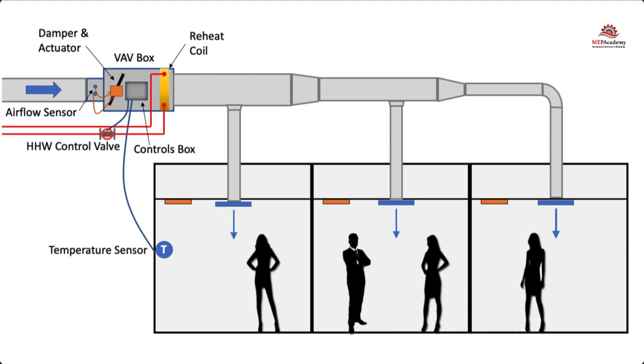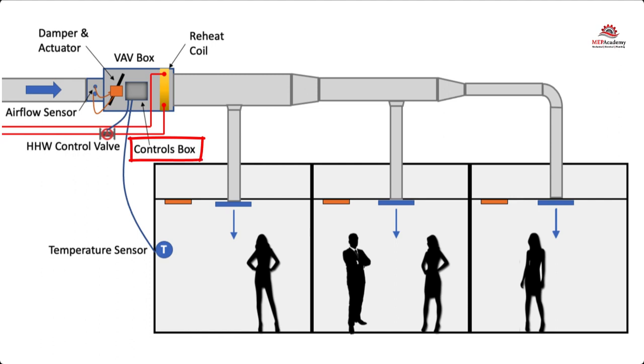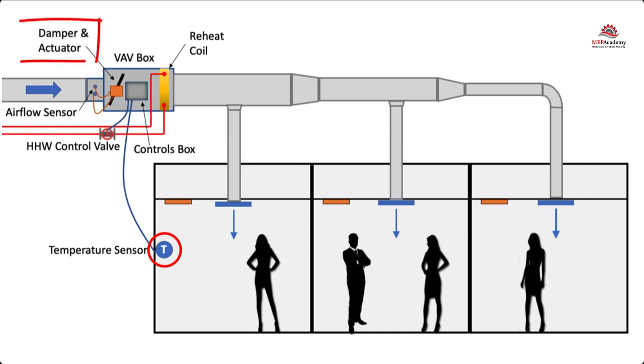The VAV box has a damper at its inlet moved by an actuator that is controlled by the controller, which takes its command from a temperature sensor. The process is very simple. When the temperature sensor in the space calls for cooling, it sends a command to the VAV box controller, which then adjusts the supply air flow rate. The adjustment is done by an actuator — which could be electric, pneumatic, or DDC; everybody's going to DDC — and it rotates the VAV box inlet damper open or closed in increments to satisfy the space requirement.